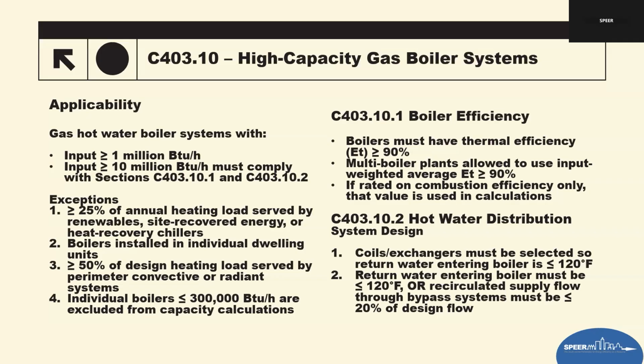The boiler efficiency: all gas hot water boilers must have a minimum of 90% thermal efficiency based on the test standards in the table. For systems with multiple boilers, the code allows an input weighted average. So you can add those together and divide to get an average for that part of it. If a boiler is only combustion efficiency rated, then that number is used for that calculation. And then hot water distribution design. This section ensures that the return water temperatures are low enough to allow condensing boilers to actually condense and achieve high efficiency. So, 2 main requirements there.